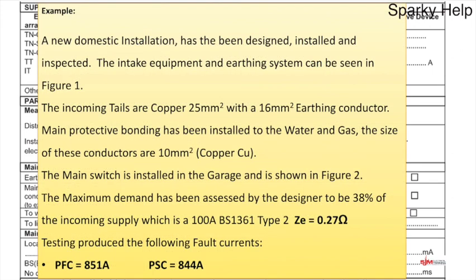Next one is fuse size. So the incoming fuse, that's the bit in the service head, the grey bit that was on the picture earlier on. And if we look there, the incoming supply, which is down here, is 100 amp BS 1361 type 2. If you're putting new installations in, they don't make a BS 1361 anymore. It's now a BS 88-3, which has replaced it. There are slight changes in the values, but it's practically the same fuse.